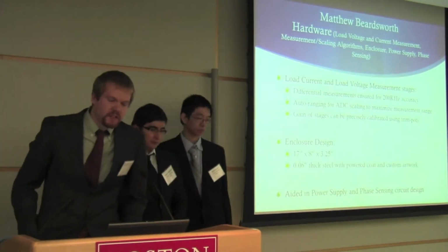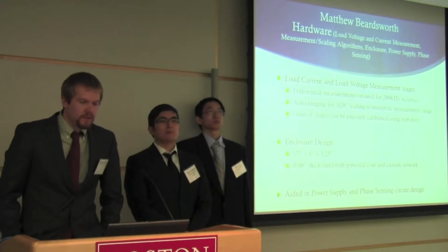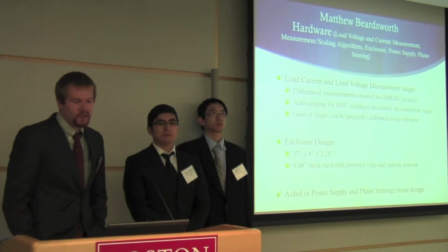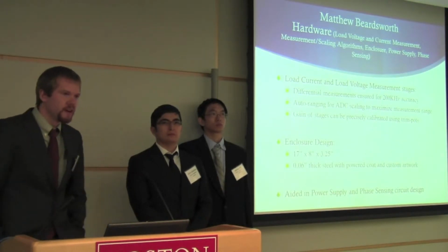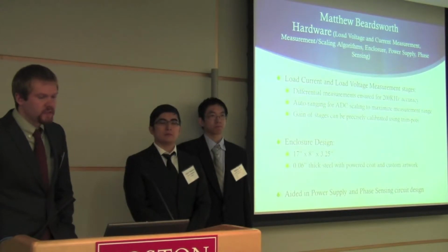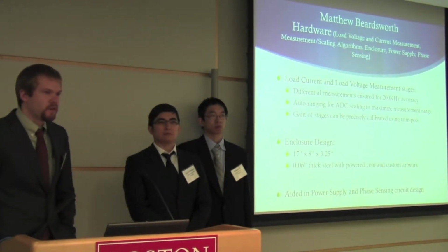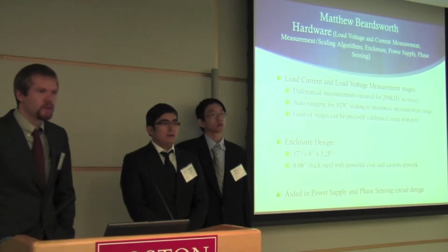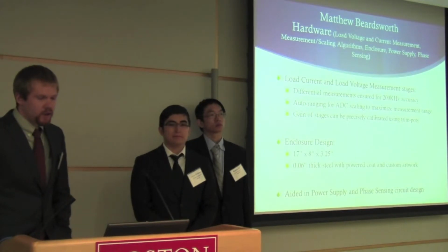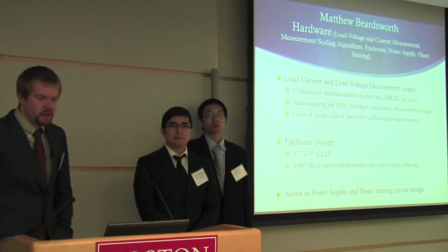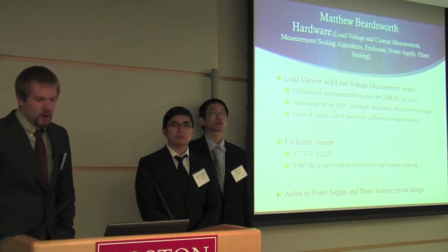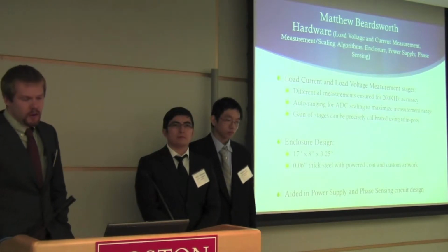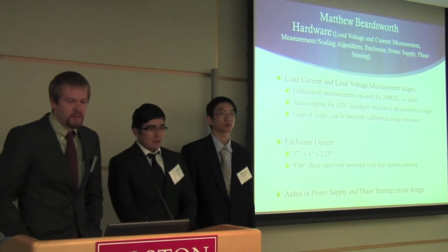So my main task for the project was developing the measurement stages. These are differential measurements of load current and load voltage. For load voltage, we can measure directly across whatever load is put in the output loop of the analyzer. For current, we're using a sense resistor setup, measuring the voltage drop across a known sense resistor and scaling it accordingly for ADC measurement, and then back calculating the current based on that known resistor value. It's all auto-ranging in order to maximize the measurement range. The scaling for, say, 1 microamp of current is a lot different than 1 milliamp. So in order to measure that with our ADCs, we have a scaling algorithm which implements automatically.